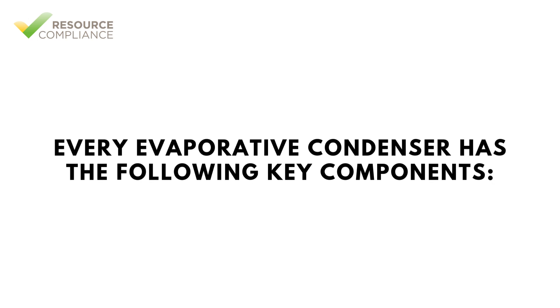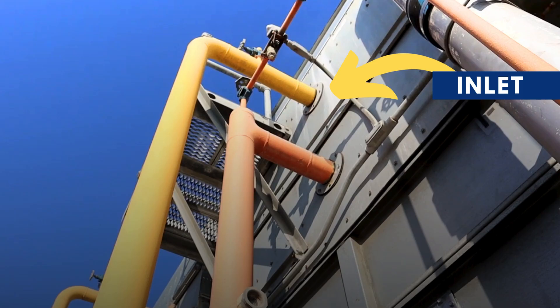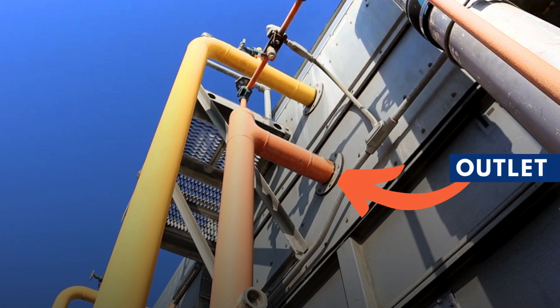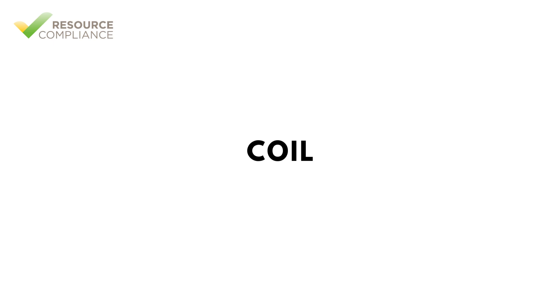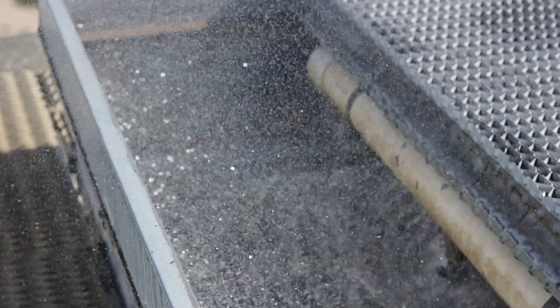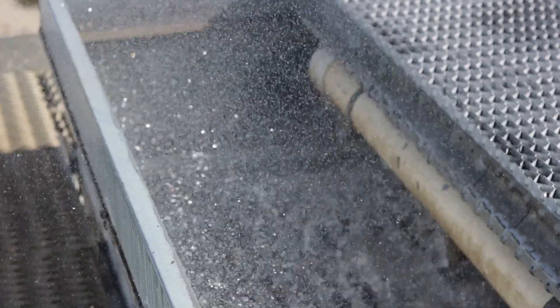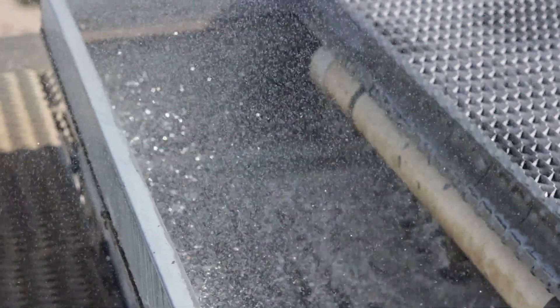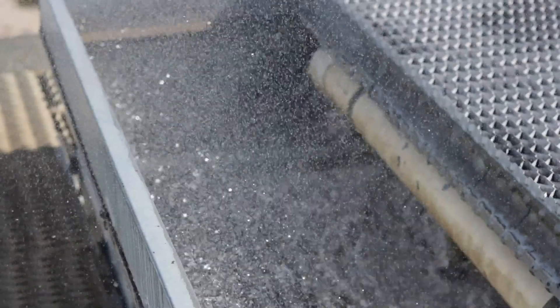Every evaporative condenser has the following key components. Each condenser will have at least one inlet connection to receive superheated vapor and one outlet connection where liquid exits the condenser. The refrigerant flows through a series of heat exchange coils made of durable materials like galvanized or stainless steel. These coils provide the necessary surface area for effective heat transfer. Water is sprayed or distributed over the exterior of the heat exchange coils, which enhances heat transfer and facilitates evaporative cooling.